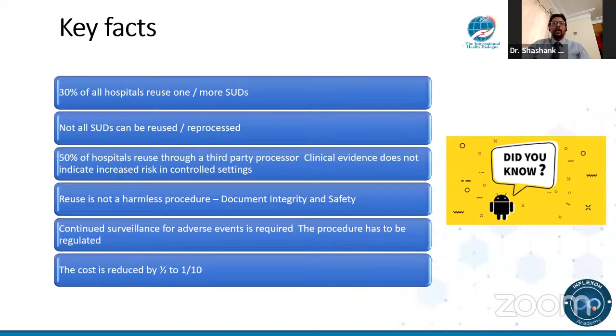Yeah, so if you look at the definition which the CDC talks about, the sterilization guidelines way back in 2008, there you would see that it clearly states that the US FDA says that if a hospital needs to reuse a single-use device in the US, now this is the older definition. Now there are a lot of hospitals saying that we cannot maintain the same sort of setup like a manufacturer. What a manufacturer has in a factory, the kind of sterility and the manufacturing process that is there, cannot be matched to something on a smaller scale that is meant in a hospital.